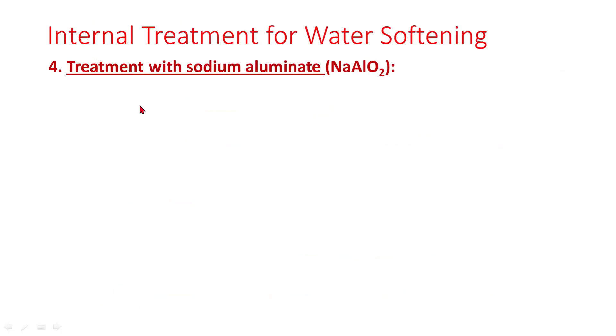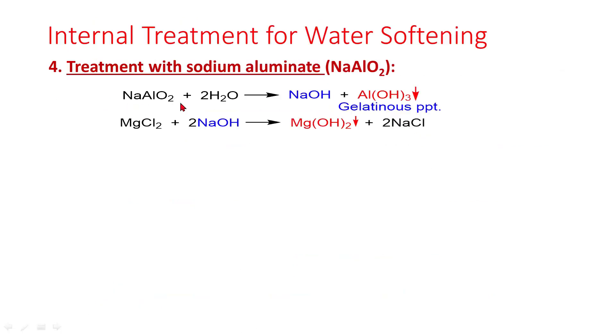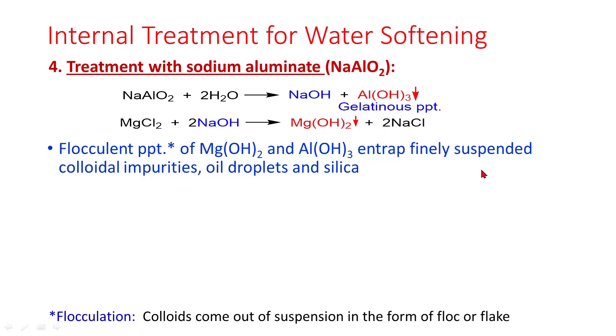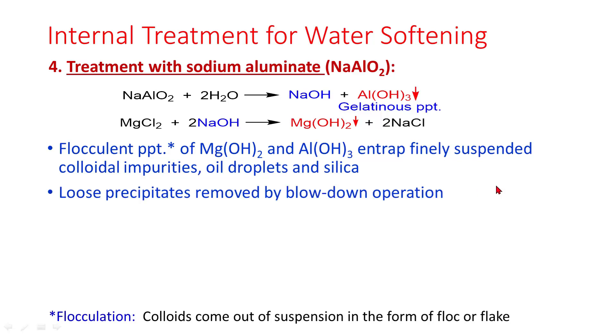Treatment with sodium aluminate: sodium aluminate with water gives rise to sodium hydroxide and a gelatinous precipitate of aluminum hydroxide. This sodium hydroxide can further react with magnesium hardness to give magnesium hydroxide. Magnesium hydroxide and aluminum hydroxide precipitates are gelatinous; they entrap finely suspended colloidal impurities, oil droplets, and silica. Loose precipitates are removed by blowdown operation.